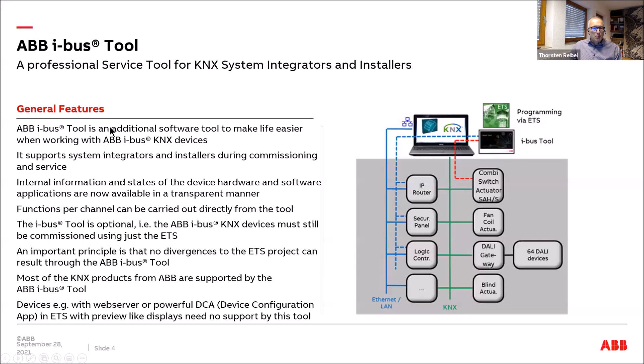Importantly, the i-bus Tool is optional — you still commission KNX devices with the ETS. It does not replace any ETS functions, and there are no differences to the ETS project: we do not reprogram anything, we only operate functions and look into components to see state information. Most KNX products from ABB are supported, but some components with a powerful DCA or a web server do not require the tool.